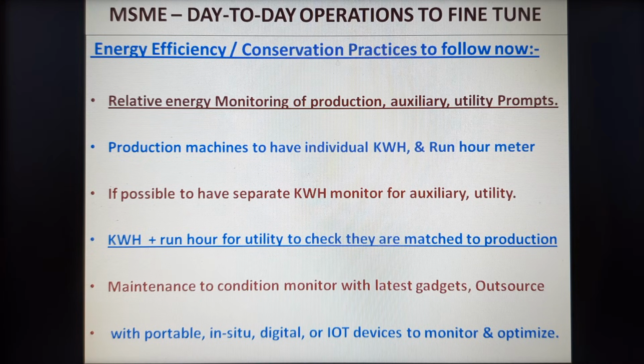The production machines or the auxiliaries or the utilities need to have an individual kWh meter and a run hour meter. I will discuss this at length later, but if it is possible, let us try to have an individual kWh meter. It doesn't cost much, around 1500 to 2000 only, but it can be installed on all your production machines, auxiliaries and utilities. With the kWh and run hour meter for the utility, you can see to it that it is matching the production.